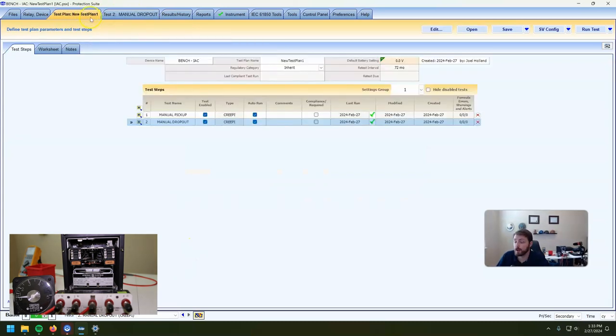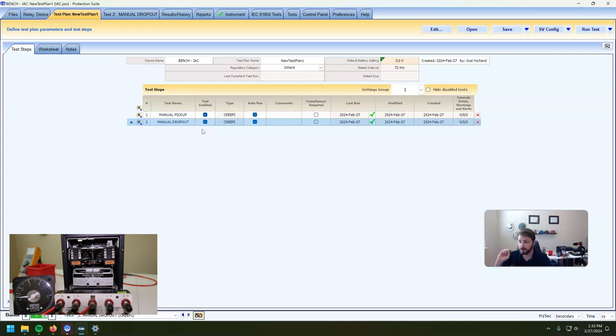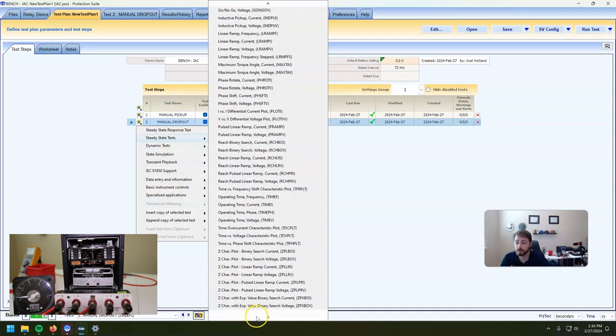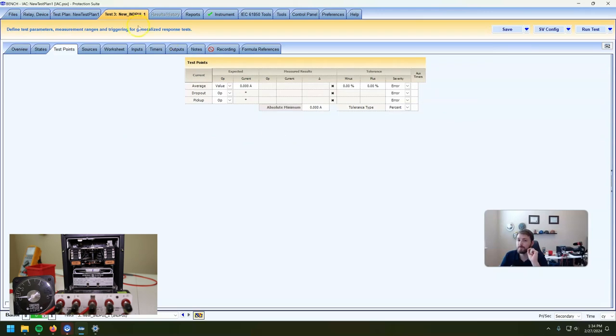How would I determine the exact amount it takes the disc to be essentially stationary — to reach equilibrium with that reset spring? RTS and the Omicron software have a very similar thing. We're going to use a prebuilt macro specific to electromechanical overcurrent pickups — an inductive pickup current test. This actually tests the amount it takes to trip and drop out. It hits it with high current to close all the way, backs off a little bit, and as soon as it sees that contact open it starts to ramp back up. We can average the dropout and the pickup very closely in very short order — that's the best pickup test.